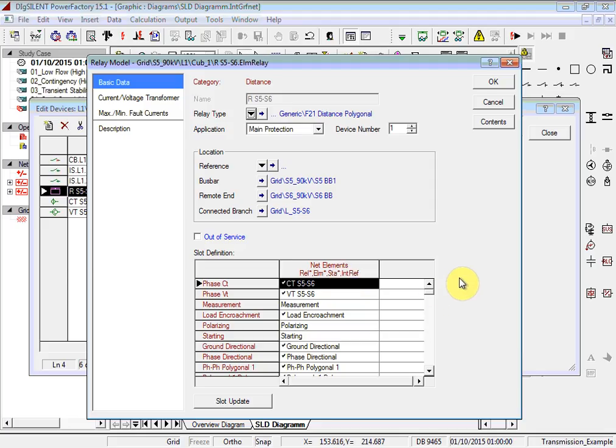Here you can see the Elm relay object. Within this object, all the settings of the relay are defined. In this example, some of the settings have already been defined. These settings are not calculated by the Distance Protection Coordination Assistant. The Distance Protection Coordination Assistant focuses on the zone reach settings, as well as the associated time delays.